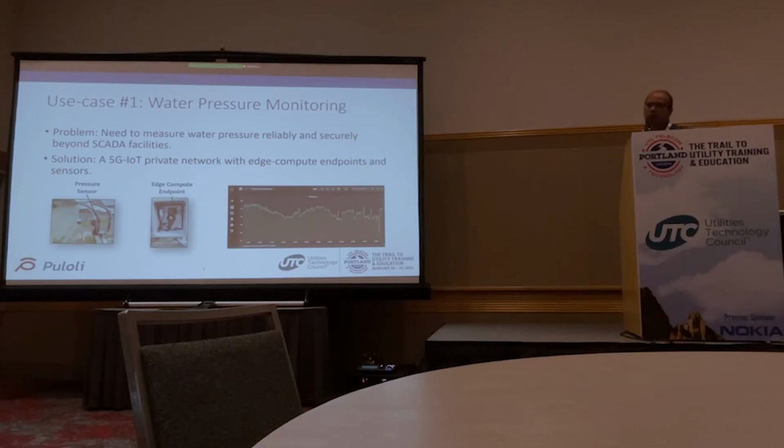This is a generation one, so the real edge compute is not a heavy compute. What's happening is that it is collecting the current loop measurement of the pressure much more frequently than what it's reporting. I think it's reporting either 5 minutes or 15 minutes back to the cloud, but it is measuring more frequently. So it is not the best example. This is 2 years ago, so it's not the best when we deployed it. It's still operational, but it was deployed 2 years ago.